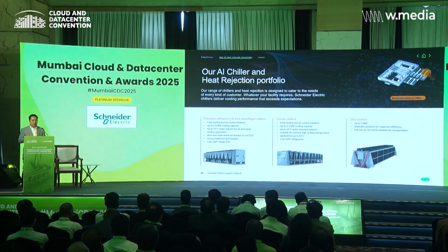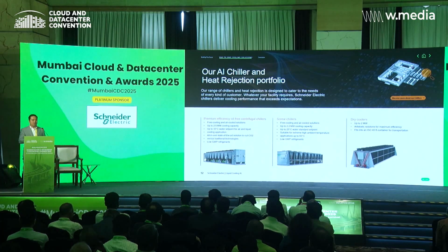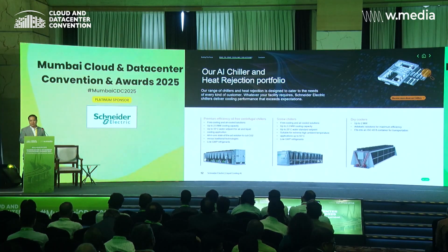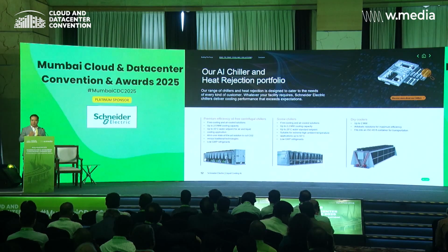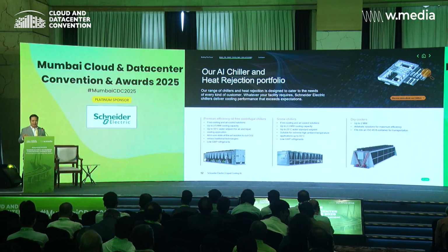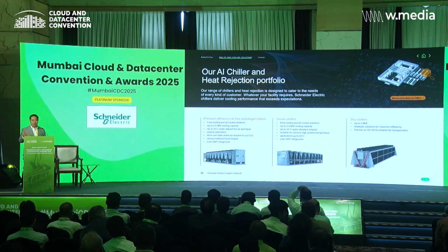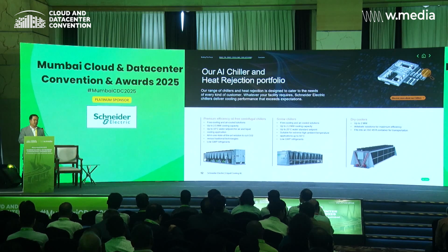This is where we offer a full range. We focus on air-cooled because access to water isn't available everywhere. We've seen instances where access to water can take 7-10 years, which means you have to rely on air-cooled in the meantime. Depending on the project and location, water availability differs, but high efficiency air-side heat rejection can be applied consistently across the globe with standard deployments.